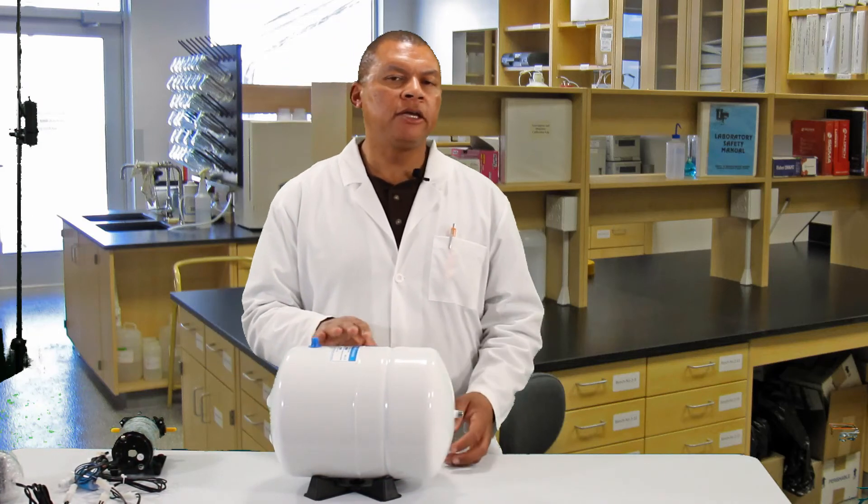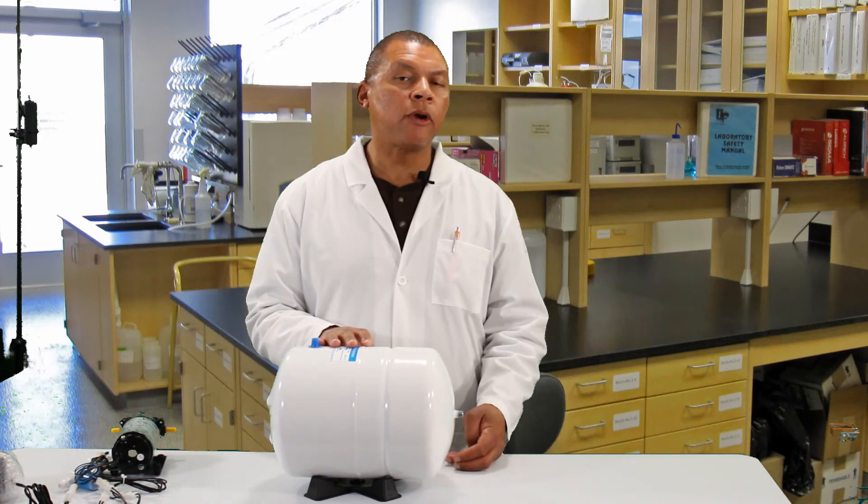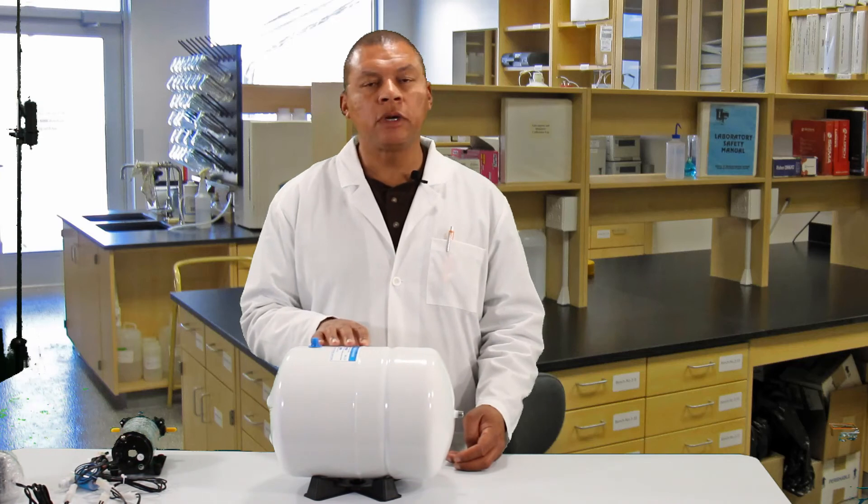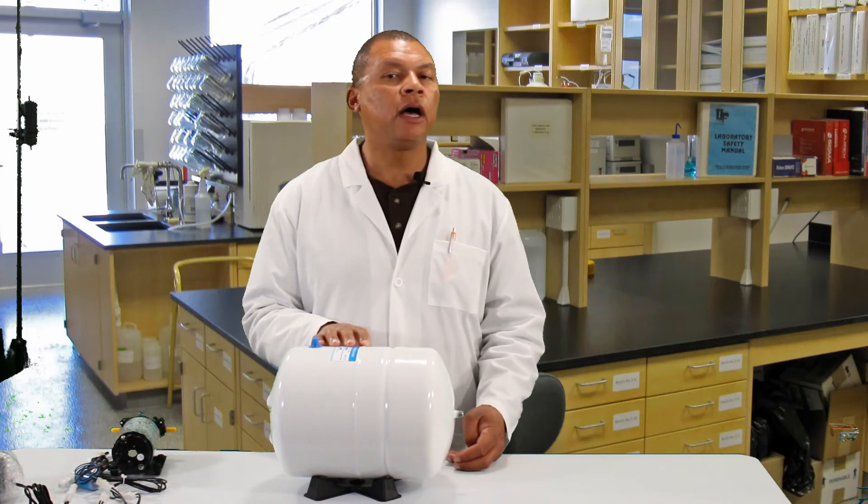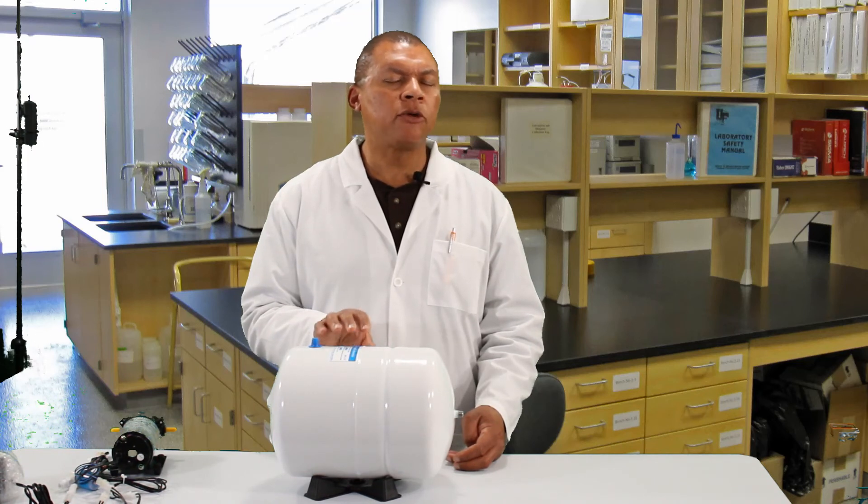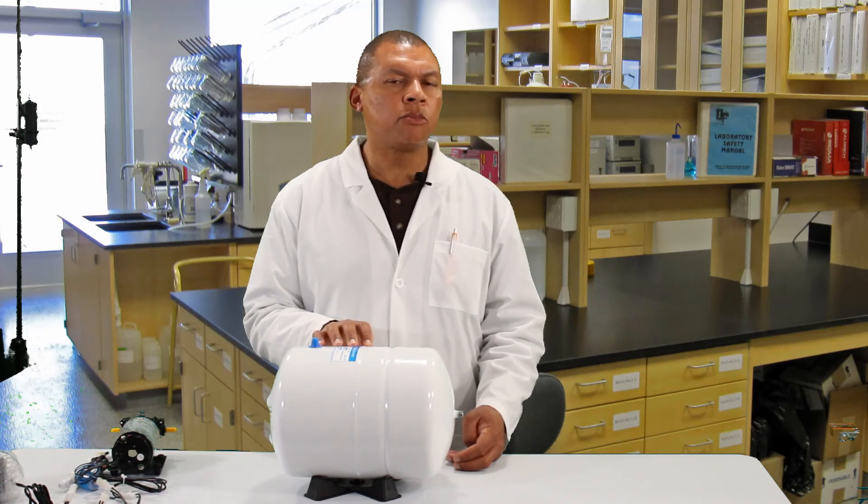Another thing to keep in mind when choosing your pressure tank, make sure that it is rated for the pressure that you are going to expose it to. This one is rated for 100 psi. So if you're working at a higher psi, make sure you adapt your pressure tank to match the working pressure that you will put on your system.